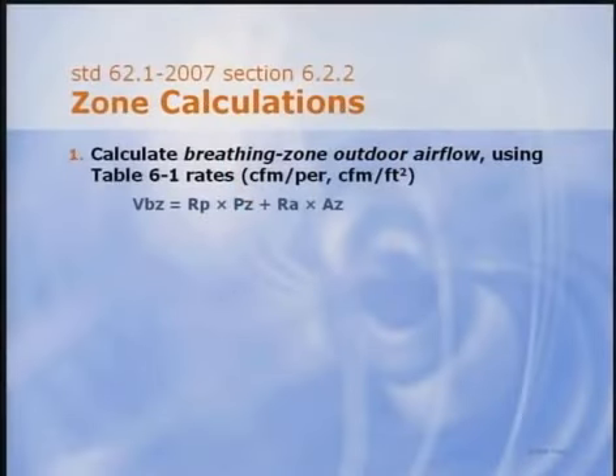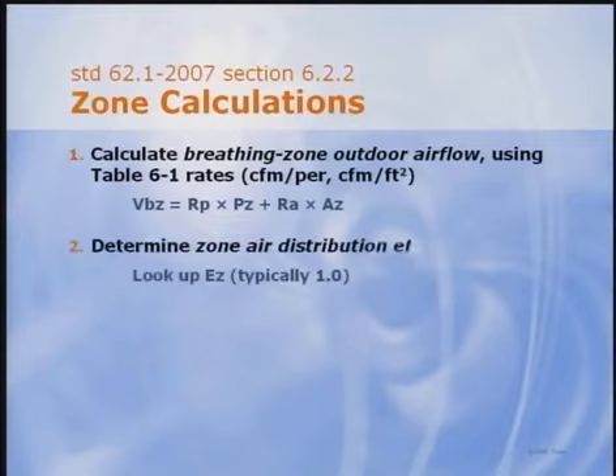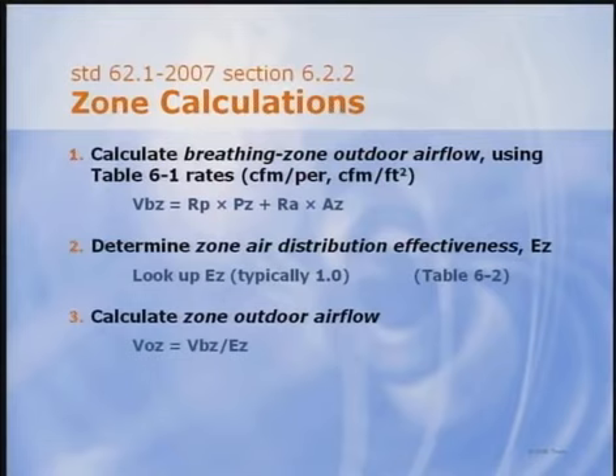For design purposes, we need to determine how much outdoor air is needed for each zone. These calculations are straightforward. First, look up the prescribed rate per person and the rate per square foot in Table 6-1. Then multiply by zone population and floor area respectively. Add these two together to find the minimum outdoor airflow required in the breathing zone. Then look up the default value for air distribution effectiveness in Table 6-2 to correct for any short-circuiting due to diffuser placement and supply air temperature. Finally, find the minimum outdoor airflow for the zone.